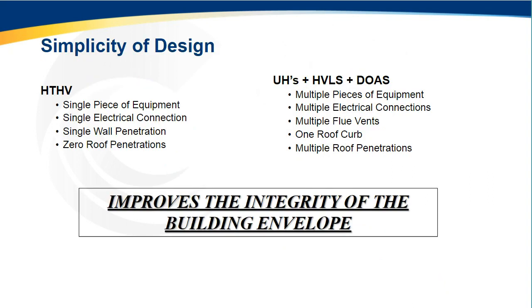So as an engineer, I love simple, and I'm sure if you're a design engineer, you love simple. You love trying to utilize one schedule as opposed to many. So think about the beauty of the HTHV technology, is that it is one single piece of equipment, one electrical connection, and one penetration. This is actually a unique story that I had with a call with an architect down in Alabama that was designing one of these systems, and they had changed their design from many indirect fired systems with many flue penetrations to ultimately about 20% of the total connected uses and actually through wall. And so the architect was actually able to completely eliminate any roof penetrations so that he was able to improve the integrity of the building envelope.